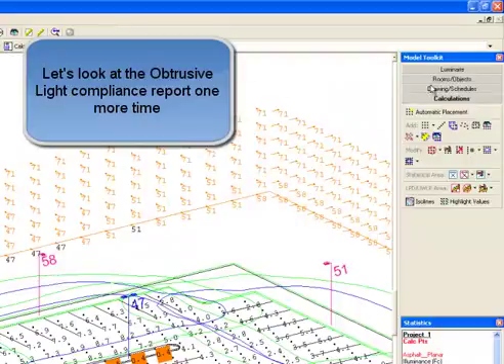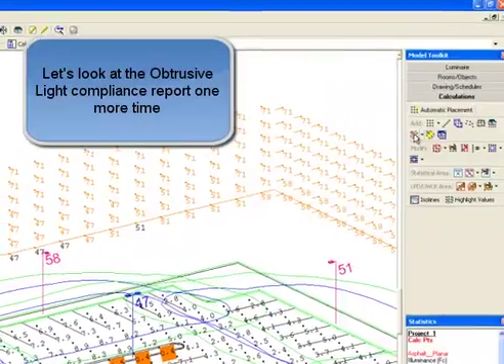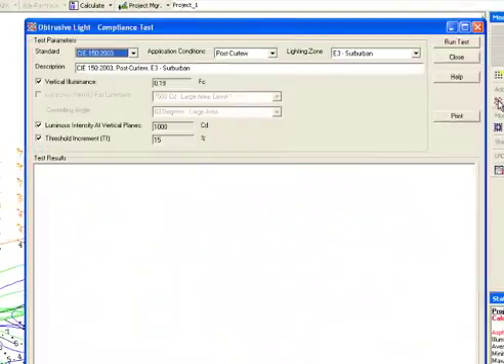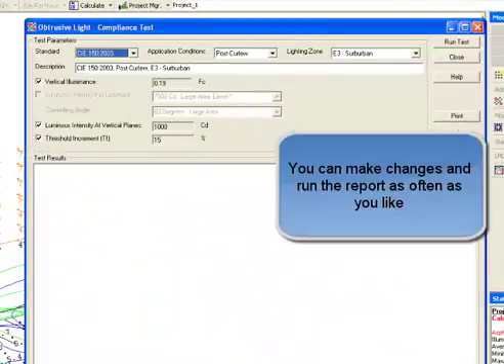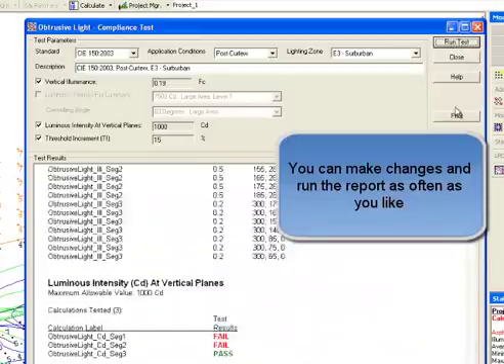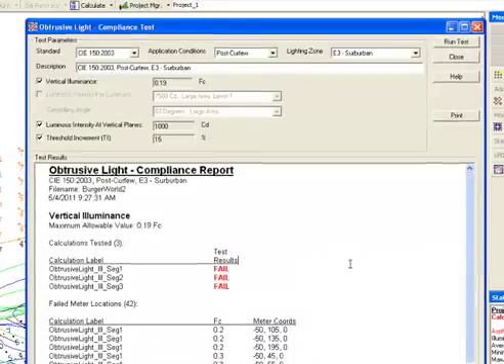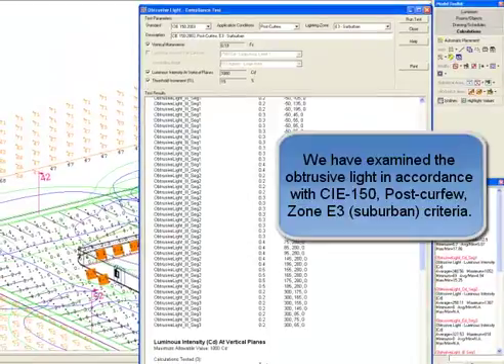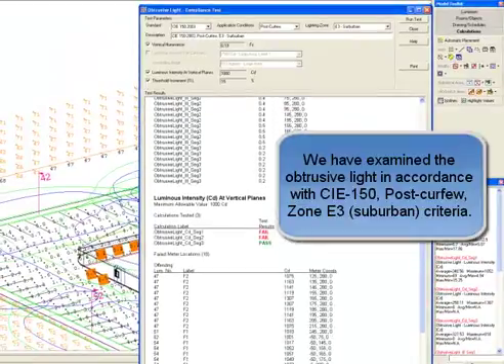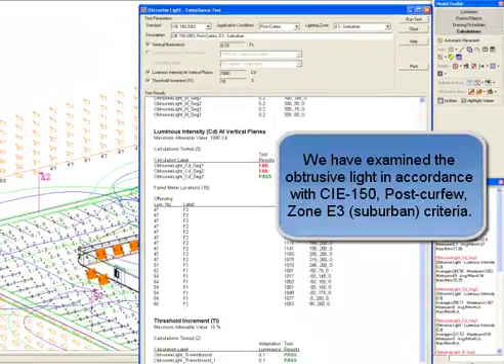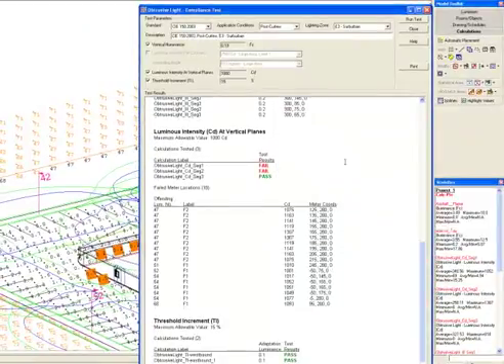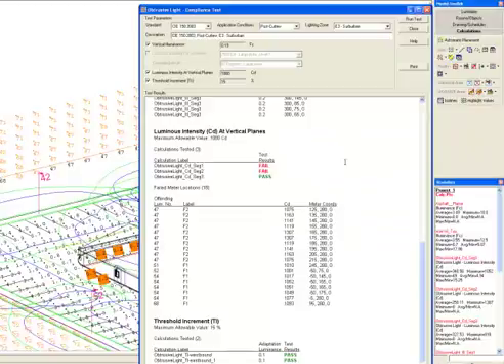Let's look at the obtrusive light compliance report one more time. You can make changes and run the report as often as you like. We have examined the obtrusive light in accordance with CIE 150 post curfew zone E3 suburban criteria.